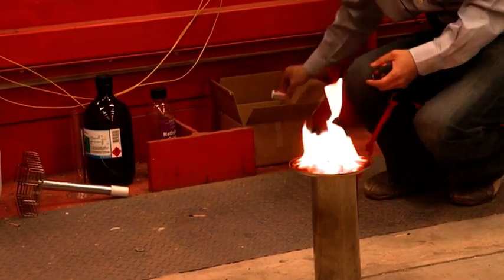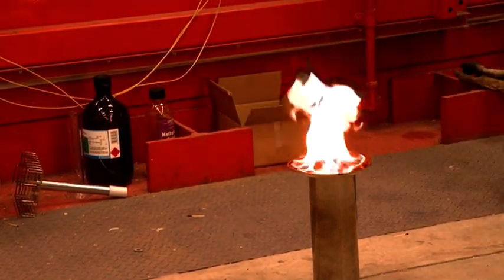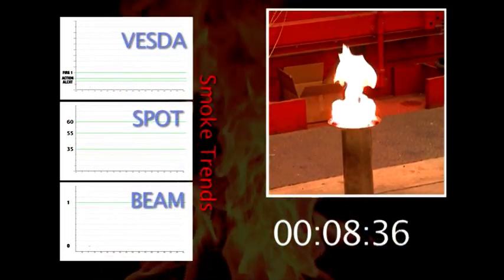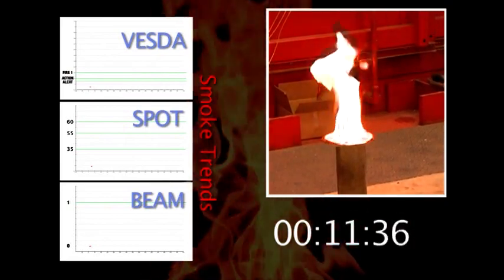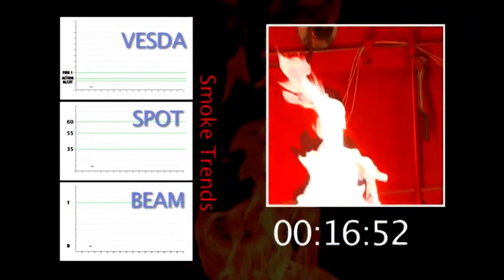Heptane. The second test is conducted to UL and EN standards and features one hundred mil of heptane to produce a fire of around ten to twenty kilowatts, which is much larger than the timber fire, yet still controllable. The burning heptane creates a large flame with black smoke.